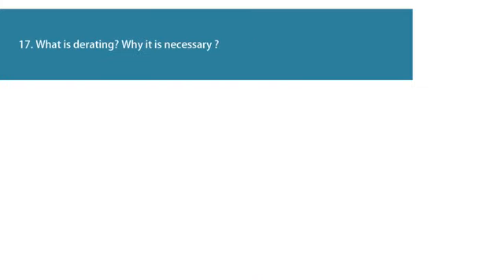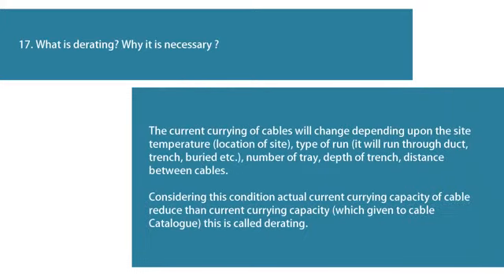Question 17: What is derating and why is it necessary? The current-carrying capacity of cables changes depending on the site temperature, location of the site, type of run — whether it runs through a duct, trench, buried, etc. — number of trays, depth of trench, and distance between cables. Considering these conditions, the actual current-carrying capacity of the cable is reduced compared to the current-carrying capacity given in the cable catalog. This reduction is called derating.